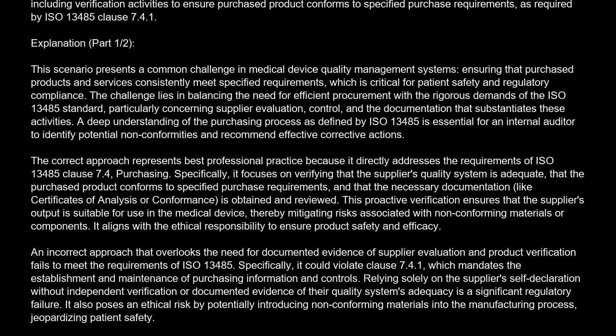The correct approach represents best professional practice because it directly addresses the requirements of ISO 13485 Clause 7.4, Purchasing. Specifically, it focuses on verifying that the supplier's quality system is adequate, that the purchased product conforms to specified purchase requirements, and that the necessary documentation, like certificates of analysis or conformance, is obtained and reviewed. This proactive verification ensures that the supplier's output is suitable for use in the medical device, thereby mitigating risks associated with non-conforming materials or components. It aligns with the ethical responsibility to ensure product safety and efficacy.